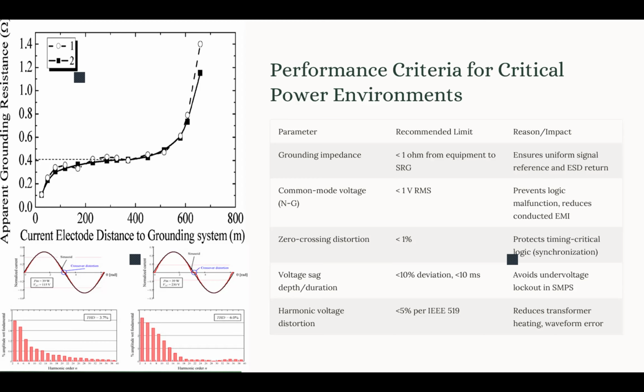Now, the criterion, the recommended limit for grounding impedance, is less than 1 ohm from the input terminal of the equipment to the SRG. So whatever wiring you use in your system to connect the plug-in of your equipment, the power supply of your equipment, to the SRG that we are developing for creating the equipotential reference plane, the connection should be less than 1 ohm.